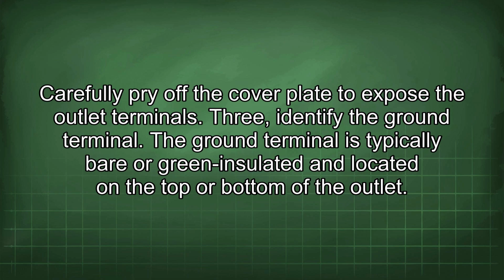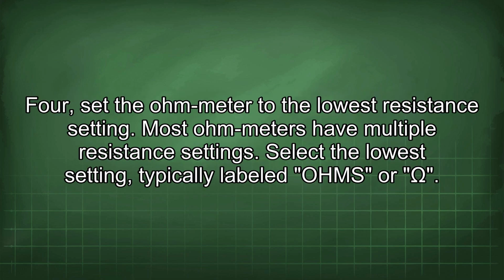3. Identify the ground terminal. The ground terminal is typically bare or green insulated and located on the top or bottom of the outlet. 4. Set the Ohm-Meter to the lowest resistance setting. Most Ohm-Meters have multiple resistance settings. Select the lowest setting, typically labeled ohms or omega.